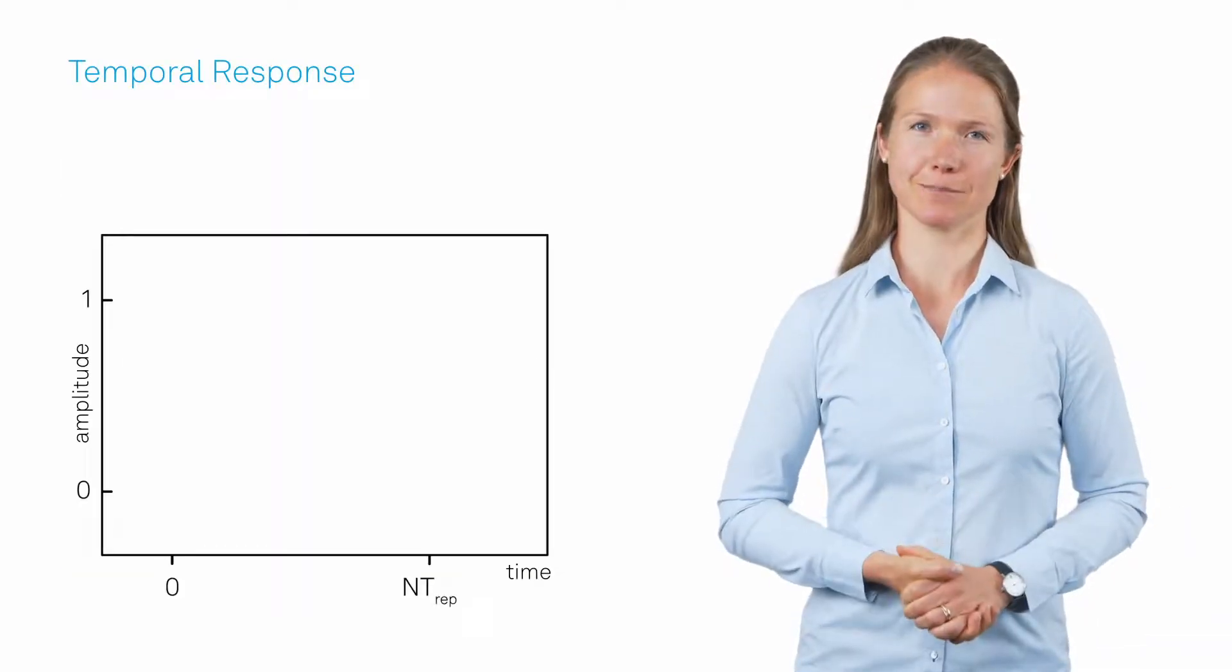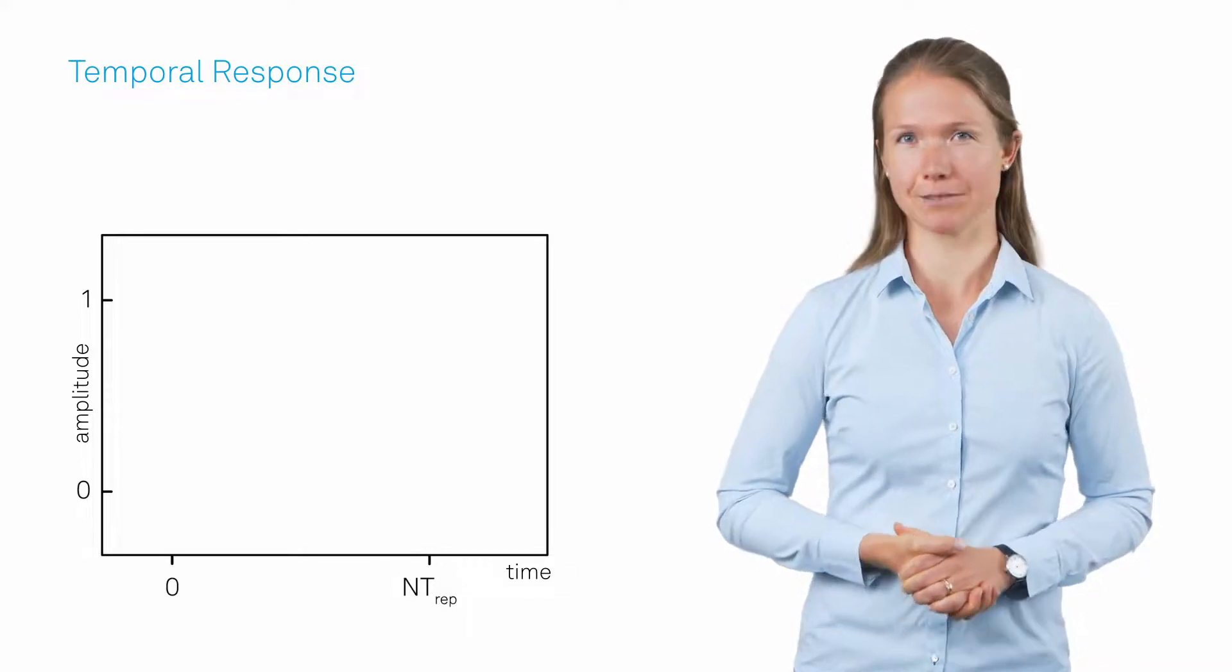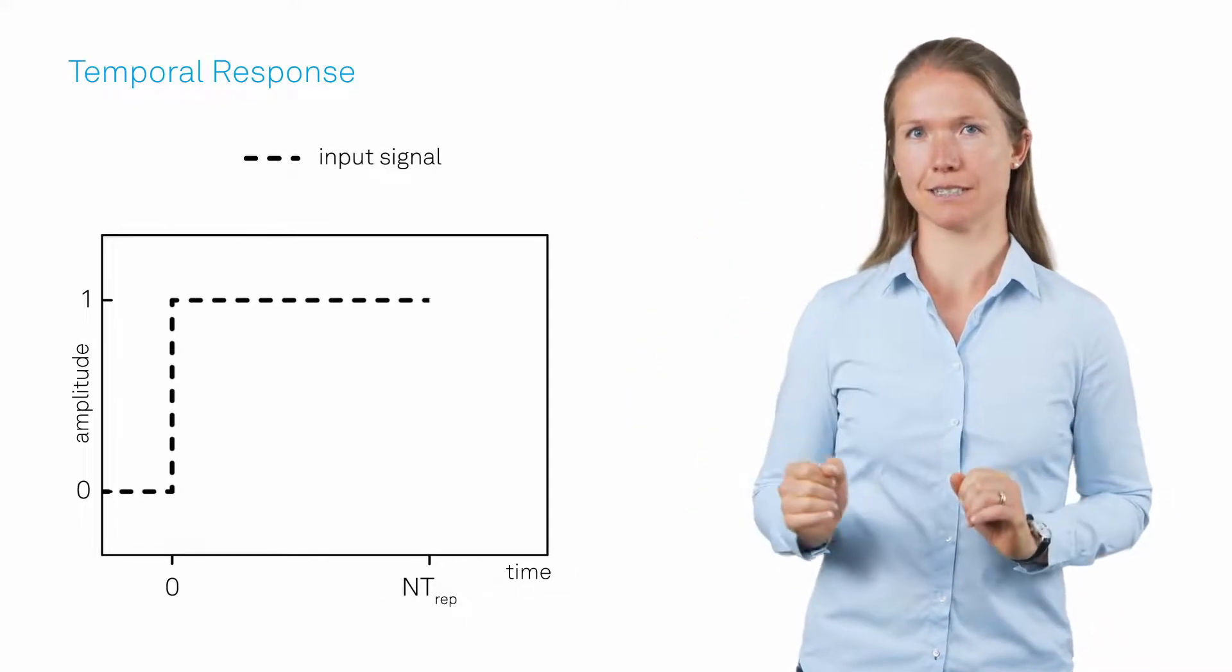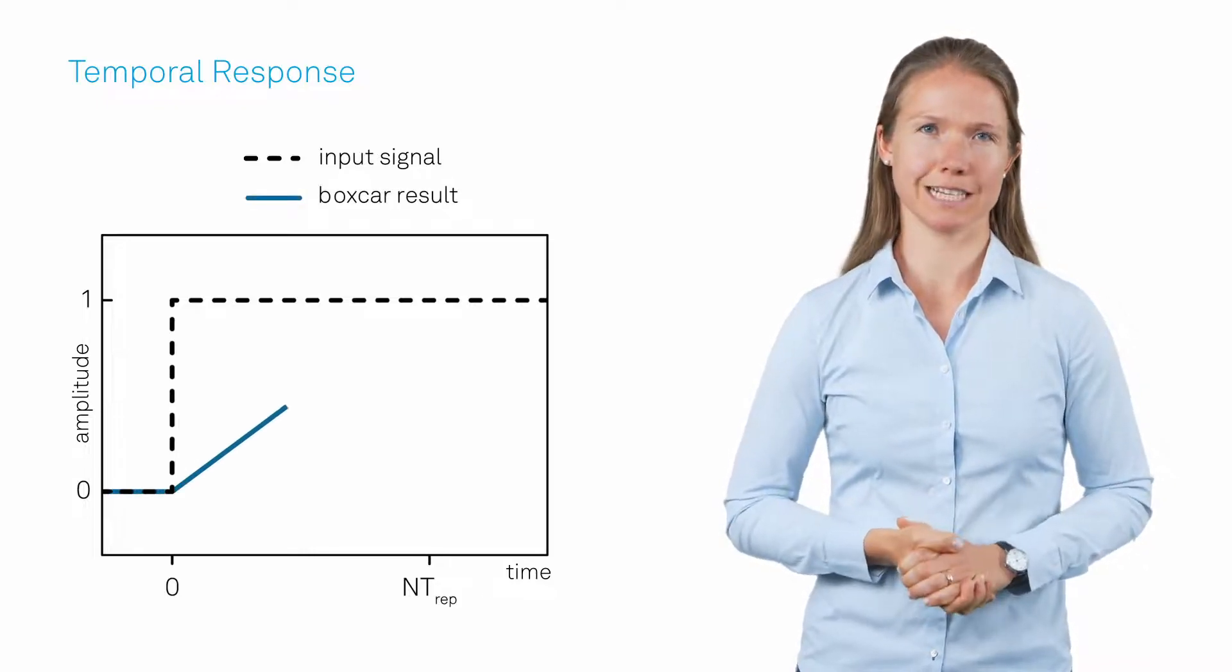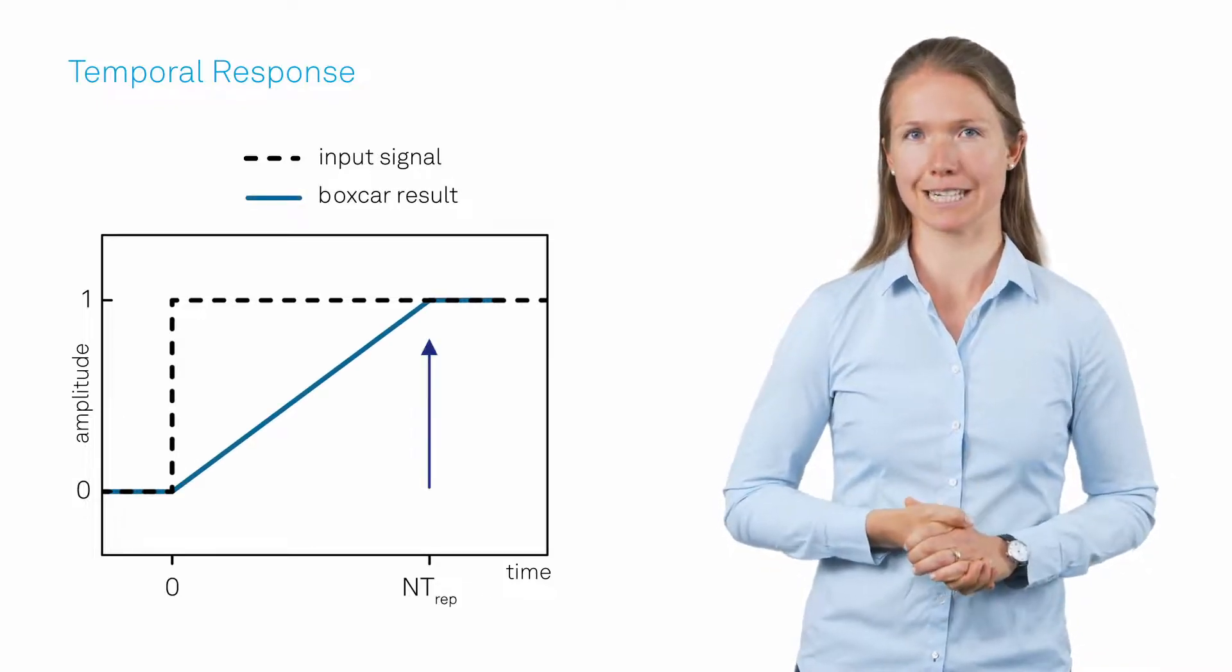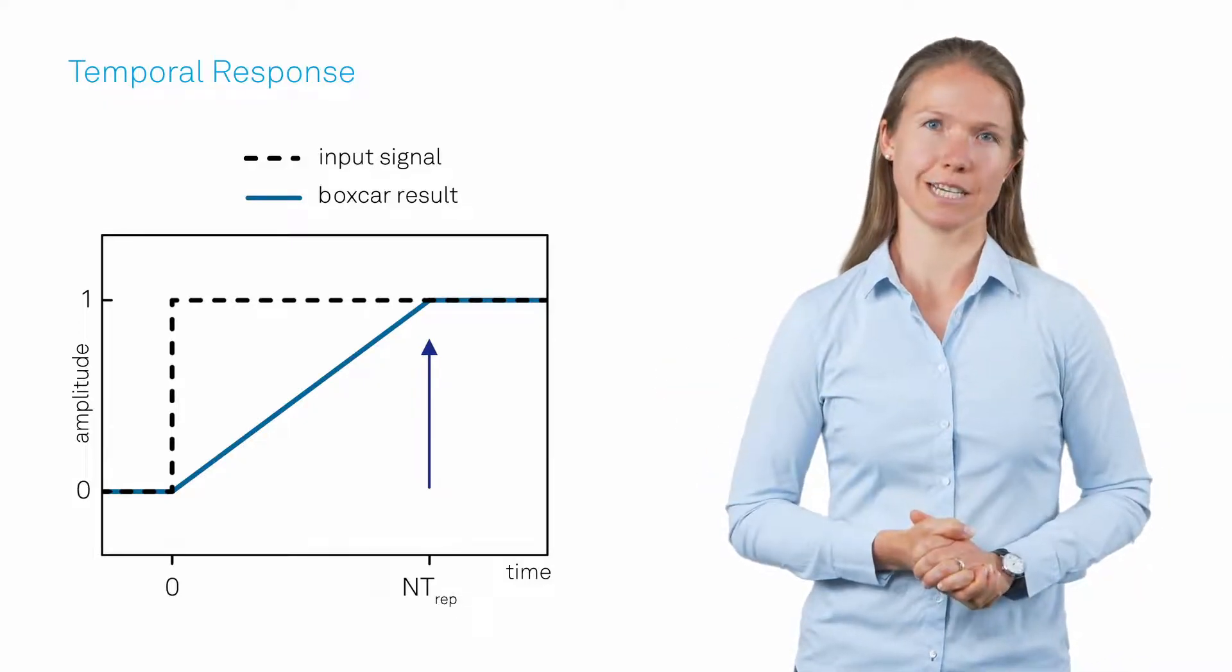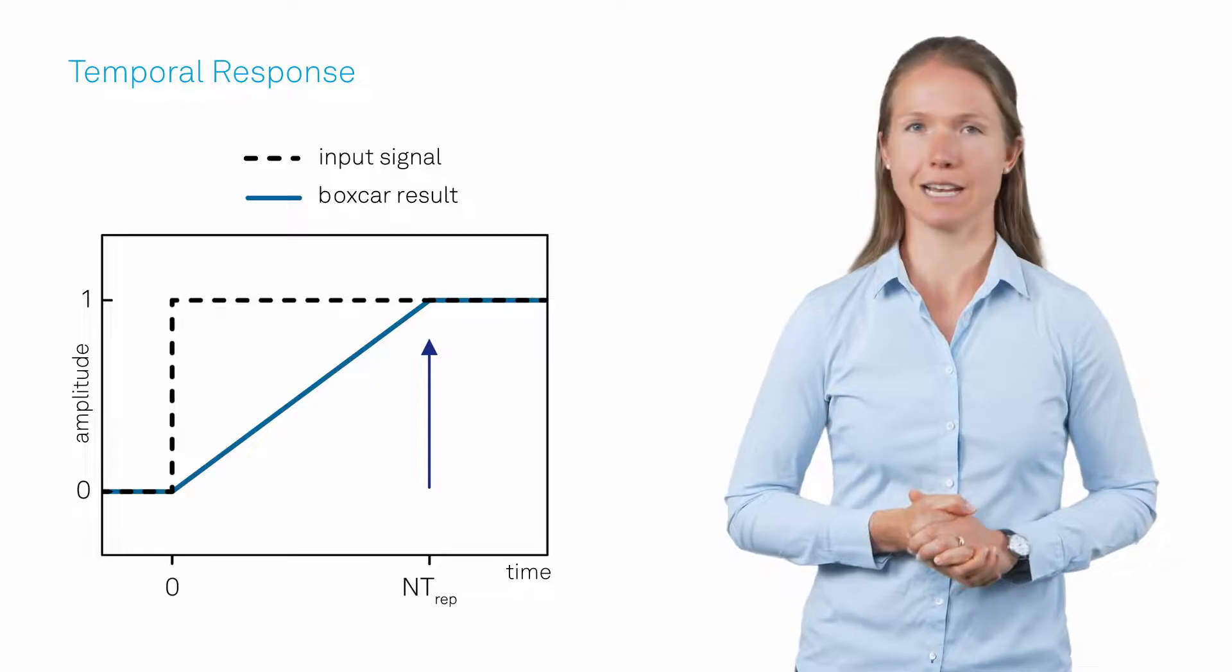However, the choice of the number of averaging periods directly affects the temporal response. After a step in the signal, the resulting value approaches the final value linearly and settles after N periods. Hence, the best choice is a trade-off between signal-to-noise ratio and measurement speed.